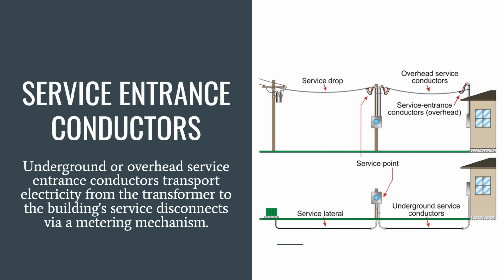Except for the neutral, which may be left bare in overhead installations, service entrance conductors must be insulated. Single-phase service drops will have 2 or 3 wires, but 3-phase service drops will have either 3 or 4 wires. Typically, the utility provides service entrance conductors. Each utility has its own requirements for wire size and minimum clearances.